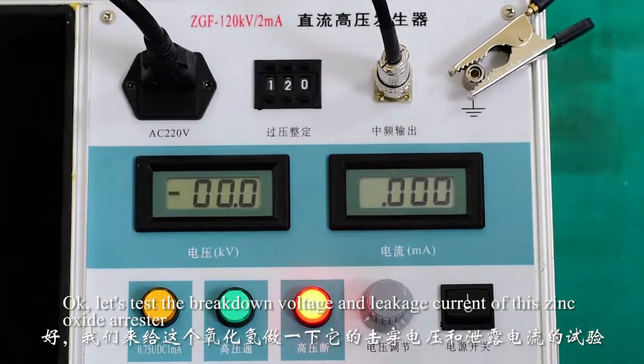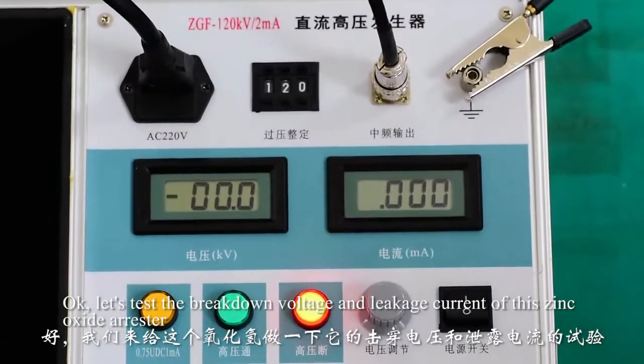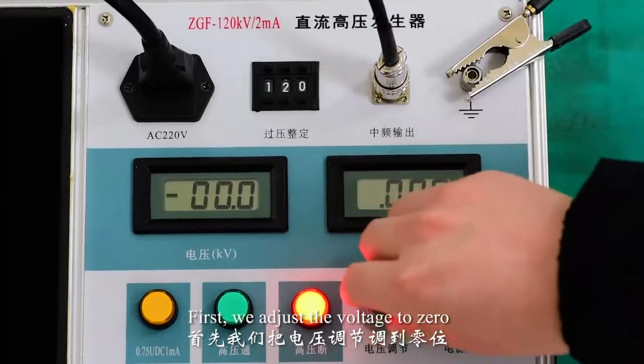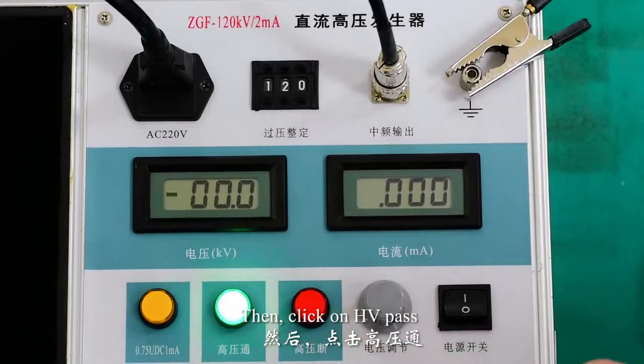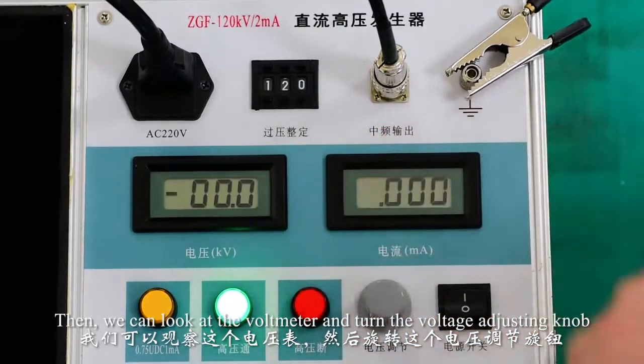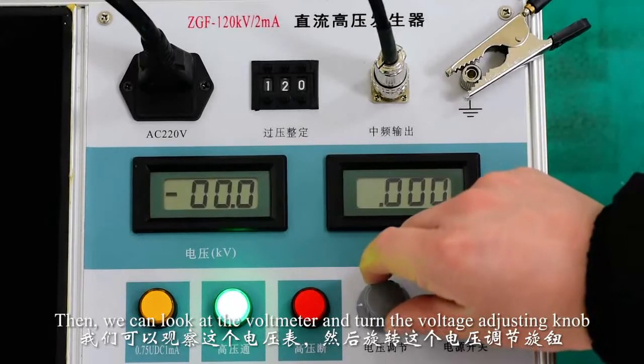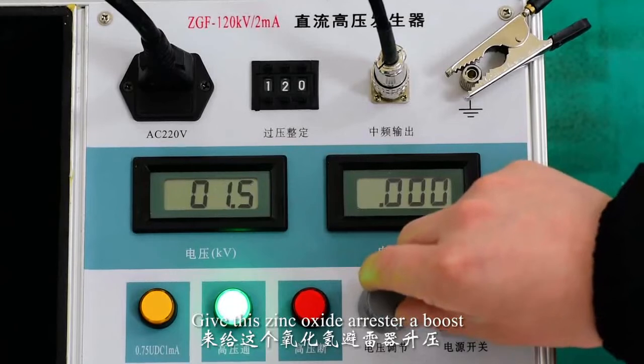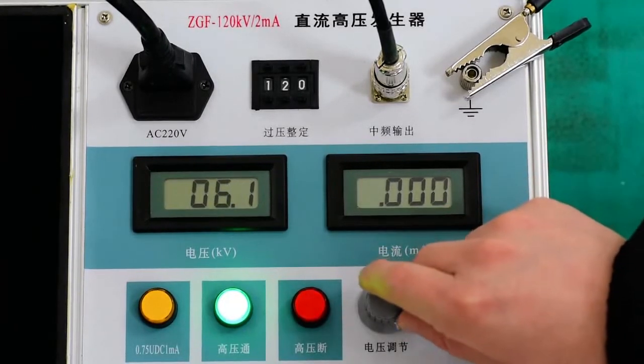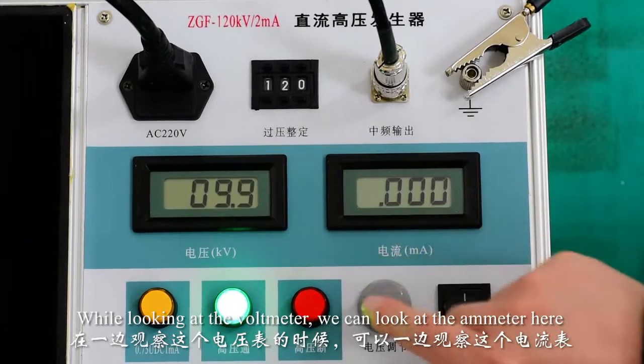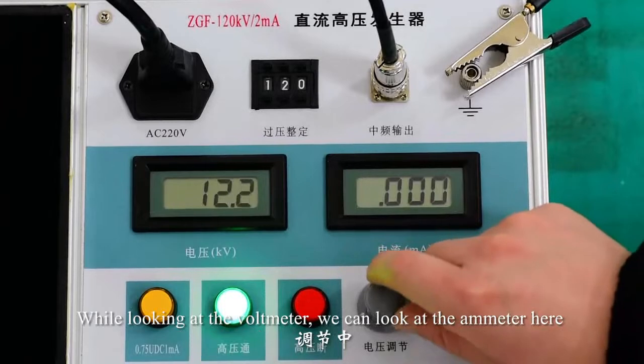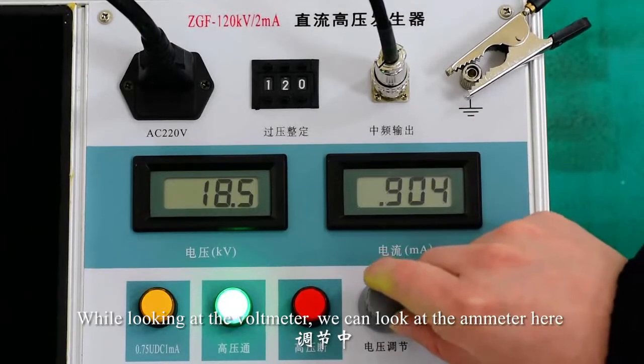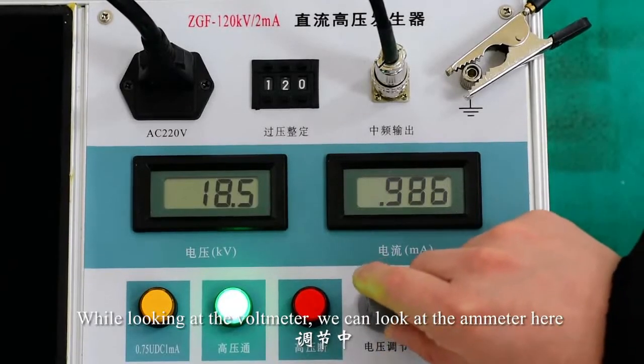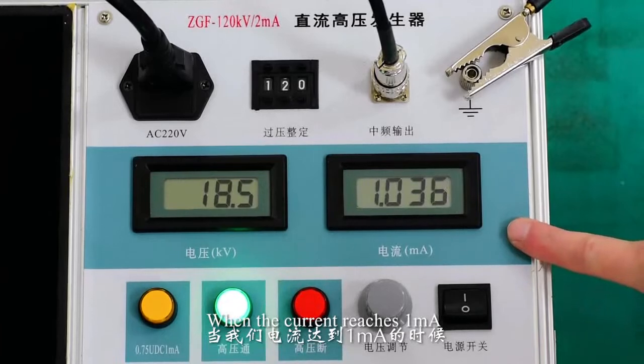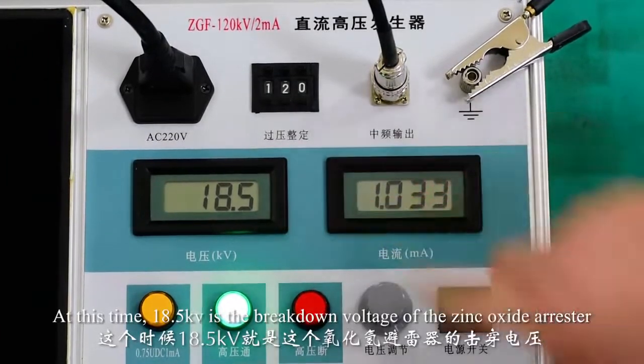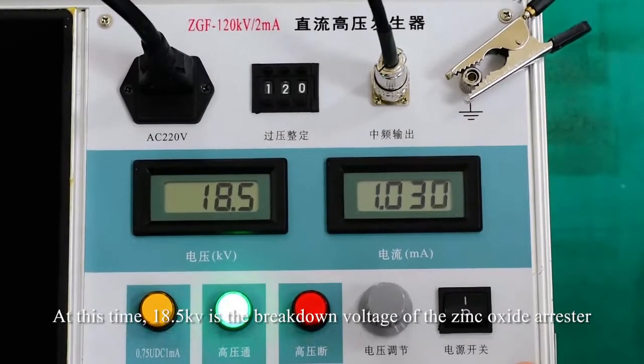Okay, let's test the breakdown voltage and leakage current of this zinc oxide arrestor. First, we adjust the voltage to zero. Then click on HV on. Then we look at the voltmeter and turn the voltage adjusting knob to give this zinc oxide arrestor a boost. While looking at the voltmeter, we also look at the ammeter here. When the current reaches 1 mA, at this time 18.5 kV is the breakdown voltage of the zinc oxide arrestor.